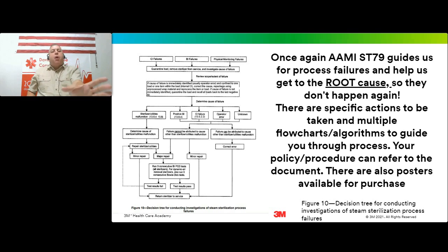You can see a smaller version of this on the left-hand side. It's figure 10 within the document. This is the decision tree for conducting investigation of steam sterilization process failures. On the top left, you can see it's telling you the CI failures, the BI failures, and the physical monitor failures. All this work was done for you.